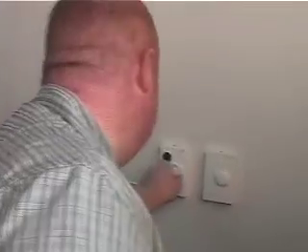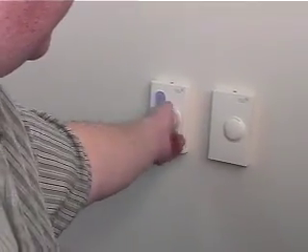By default, you can go from 55 to 85. Right. We need to maintain a more consistent temperature. Well, it's a 4 degree deadband, but our adjustability on it, I believe, is 68 to 74. We can actually look at it really quickly. If you rotate the dial, yeah, 68 is the coldest, and the warmest is 74. Yep. So that should help eliminate some of those calls. Yeah, that'd be cool.